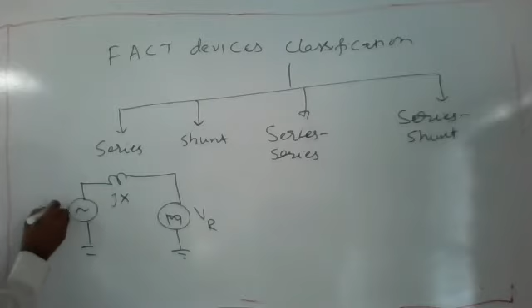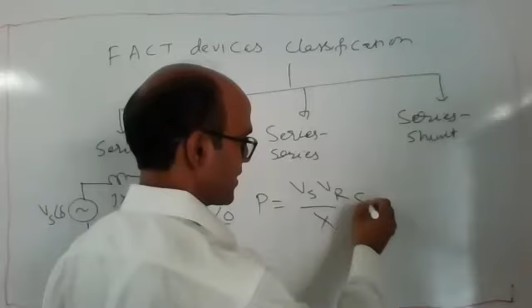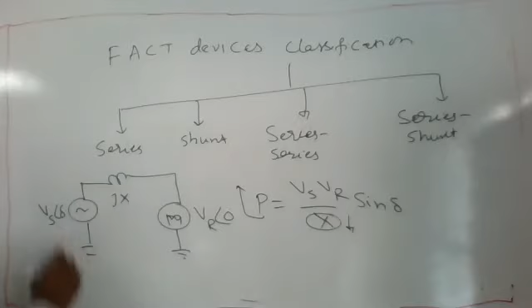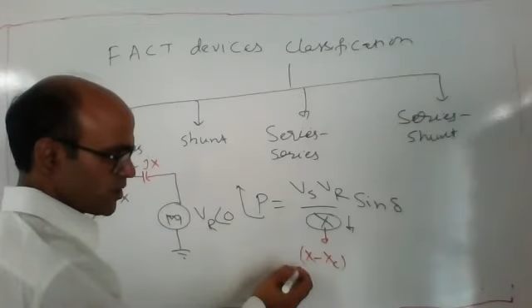Okay, and you have derived the power for this system, P equal to E V by X, real power. That is, sending end voltage into receiving end voltage divided by X into sine delta. These ES, ER, X are the magnitudes. So this you know, real power. Okay, so how to increase this power? If we decrease this reactance, then we can easily increase this real power. So how do I decrease this reactance? By connecting a series capacitor. So this is one of the compensation devices. If I insert a series capacitor like that, then this is minus jXc. So overall, this reactance modifies to X minus Xc. So you can see X is reduced in this case. Okay, so this is the series compensation. So first one is series compensation.